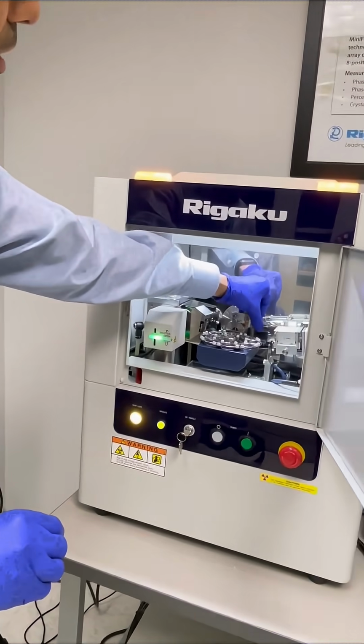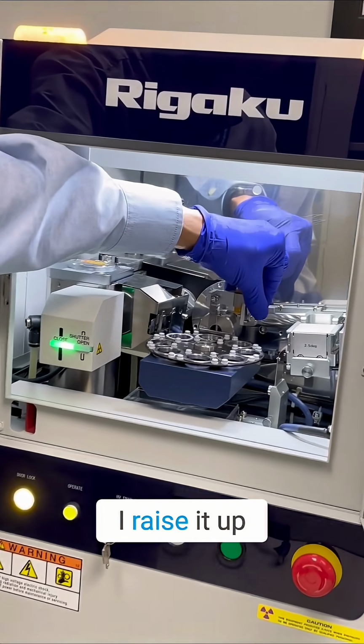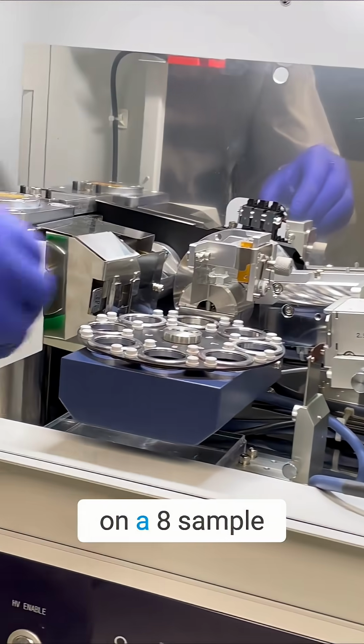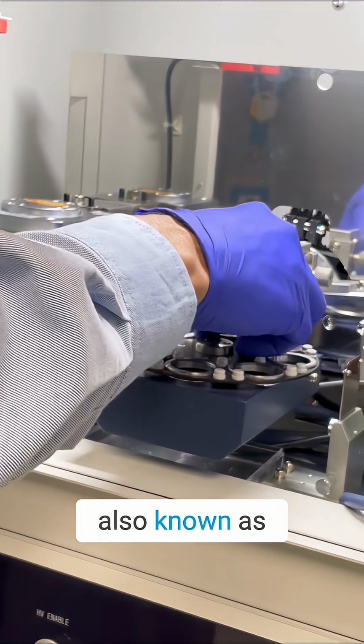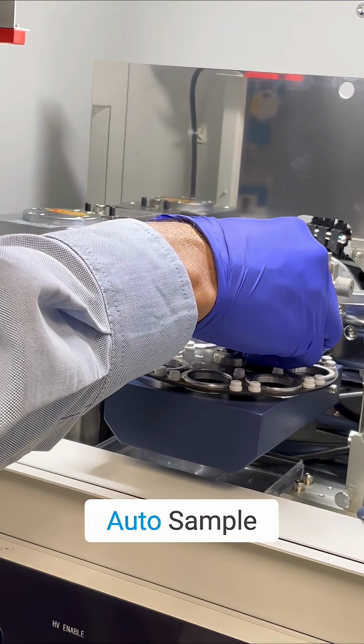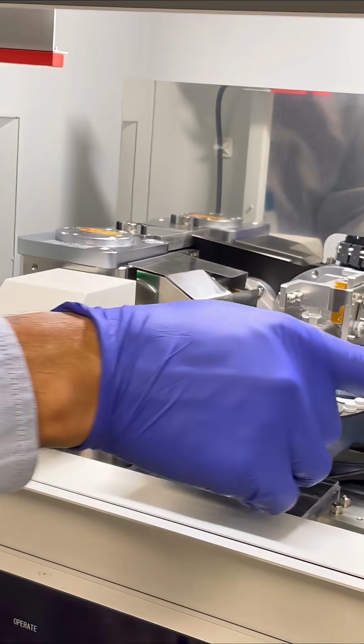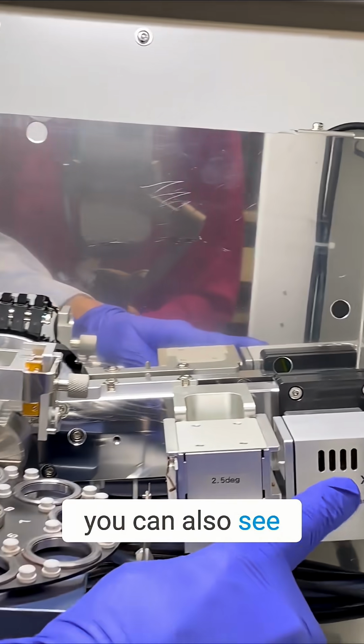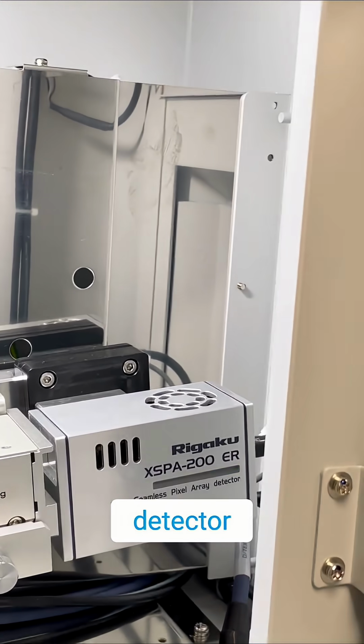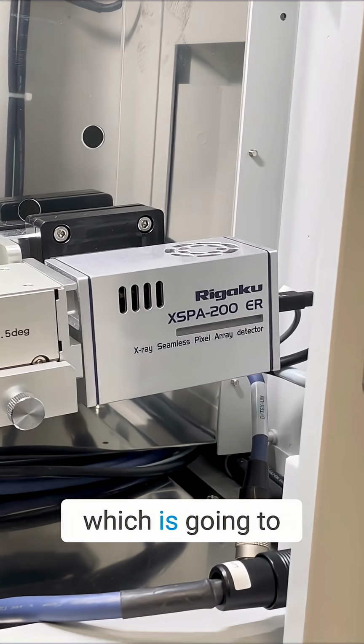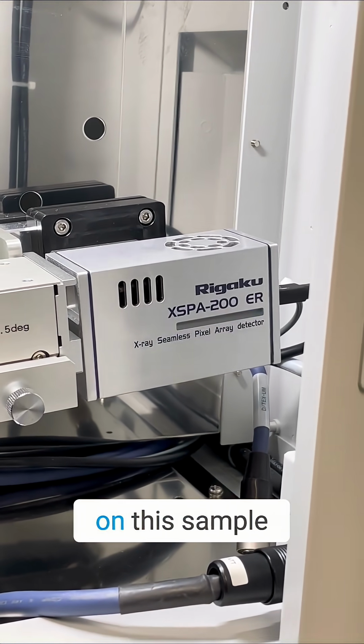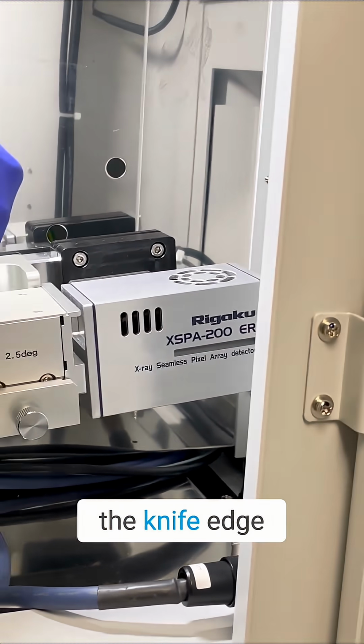And the knife edge, I raise it up to put the sample on the sample changer, also known as Rigaku's ASC8, Auto Sample Changer 8. And here you can also see the XSPA-200 ER detector, the pixel array detector, which is going to give us excellent data on this sample. I'm going to lower the knife edge.